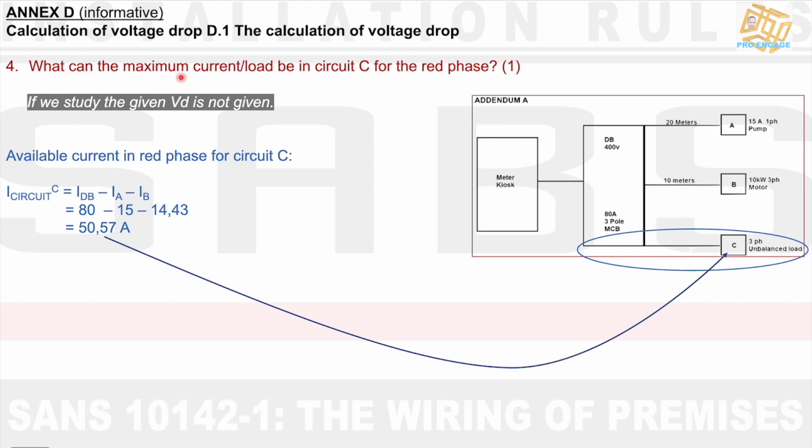Part 4 of this question, what can the maximum current load be in circuit C for that red phase? We can simply just say I circuit C equals I DB minus the current in circuit A minus the current in circuit B. And we found that in circuit A, the current was 15 amps. We found there. And the current in circuit B was that power there divided by 230, or sorry, 400 √3. And we got an answer of 14.43 amps. If we do this calculation, we get an answer of 50.57 amps. The current there in the three-phase unbalanced load is equal to 50.57 amps.